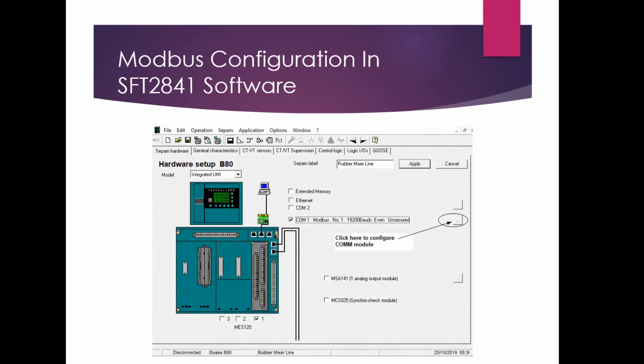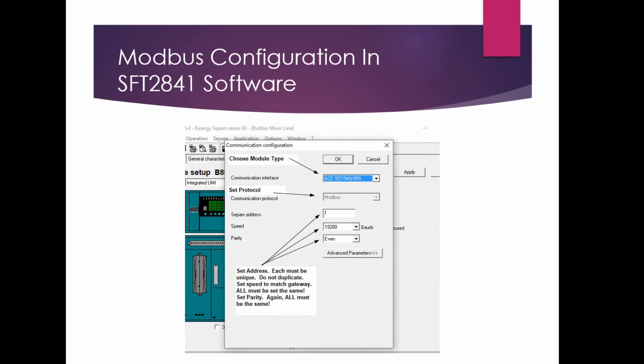In your SFT 2841 software you configure your comm module by clicking on the little box to the right of — for example here we're using Comm1. Once this opens up, make sure you choose the correct module type. The protocol will be Modbus and you set the Sepam address — you cannot have more than one module with the same address; each one has to be unique. The baud rate needs to be the same for everything on that string, and same with the parity — you can't have odds, evens, and nones all on the same string.